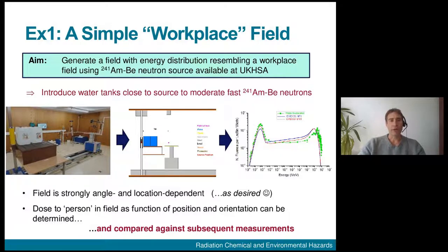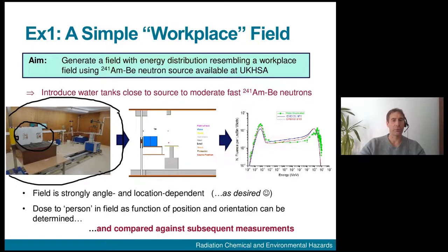Okay, so that's the theory. Of course, it's important to test it, and we tested it by building a very simple simulated workplace field in our neutron laboratory. So this here on the left is the secondary standard neutron field in UKHSA, and we have here, behind this lead shield, an AmBe source. We then introduced the water tanks behind that AmBe source in order to moderate the field.